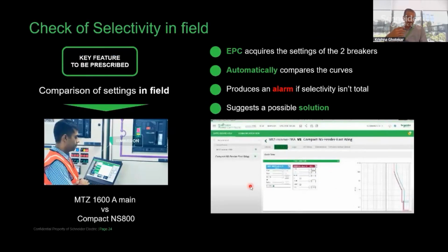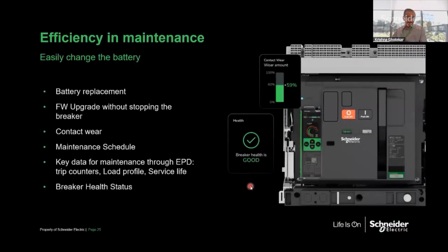Selectivity, as I mentioned, is again a first for a circuit breaker in the electrical market: you can check the selectivity using the EPC software between MTZ Active and the downstream breaker. Maintenance indicator: you can do a battery replacement, you have contact wear and tear, and you can do maintenance scheduling, like after 1 year or 2 years. There will be a display on your application, EPD, that the breaker has seen this operation and this maintenance is to be done. If it is 5 years later, what maintenance is to be done, how to do it, whether it can be done easily or you need a service engineer, all those details come in this maintenance schedule.